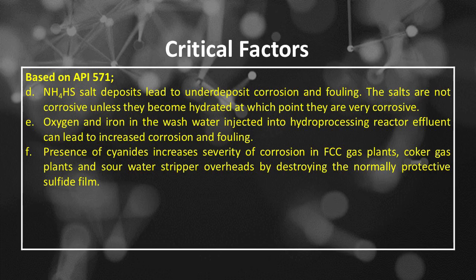The salts are not corrosive unless they become hydrated, at which point they are very corrosive. Number E: oxygen and iron in the wash water injected into hydroprocessing reactor effluent can lead to increased corrosion and fouling. Number F: presence of cyanides increases severity of corrosion in FCC gas plants, coker gas plants and sour water stripper overheads by destroying the normally protective sulfide film.